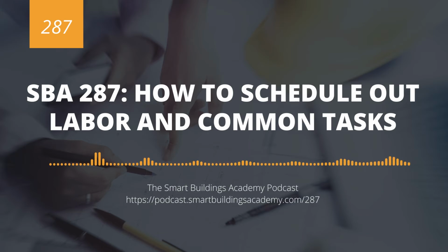That's when subcontractor line out happens. Maybe we need a day to support subcontractor line out, so that's 8 hours. And then let's say month 4 and a half, month 5, subcontractors are done, and let's say the mechanical startup is done and electricity is working, then we're going to start our point to point. And so maybe we pull 32 hours into month 5, month 6. And so I start moving around my hours. While I had them evenly distributed across my months, I now start to pull them into the months that are appropriate. And all the while, I have this master list of hours.